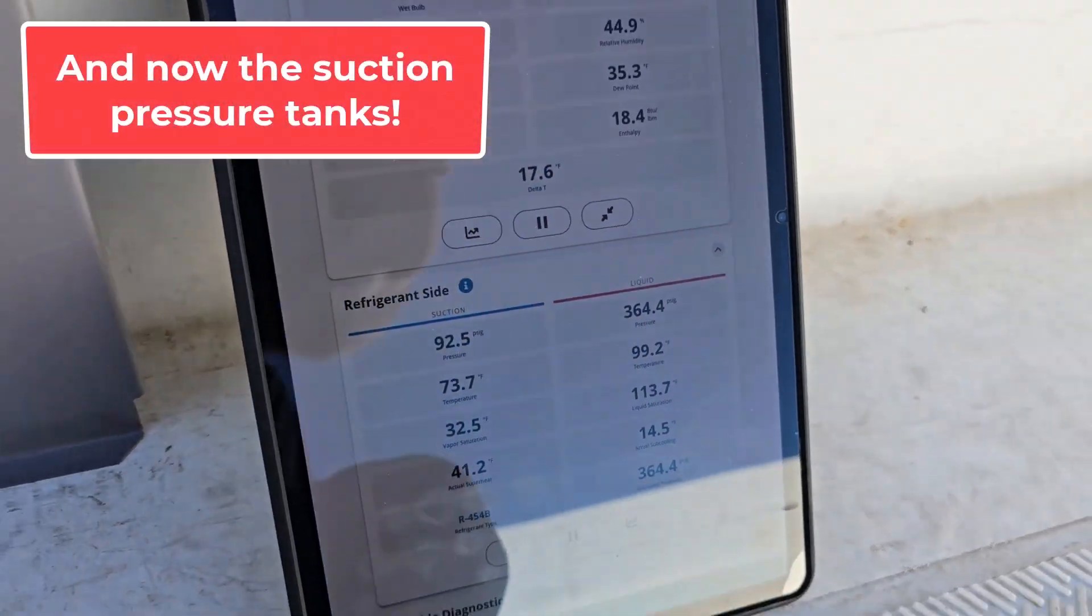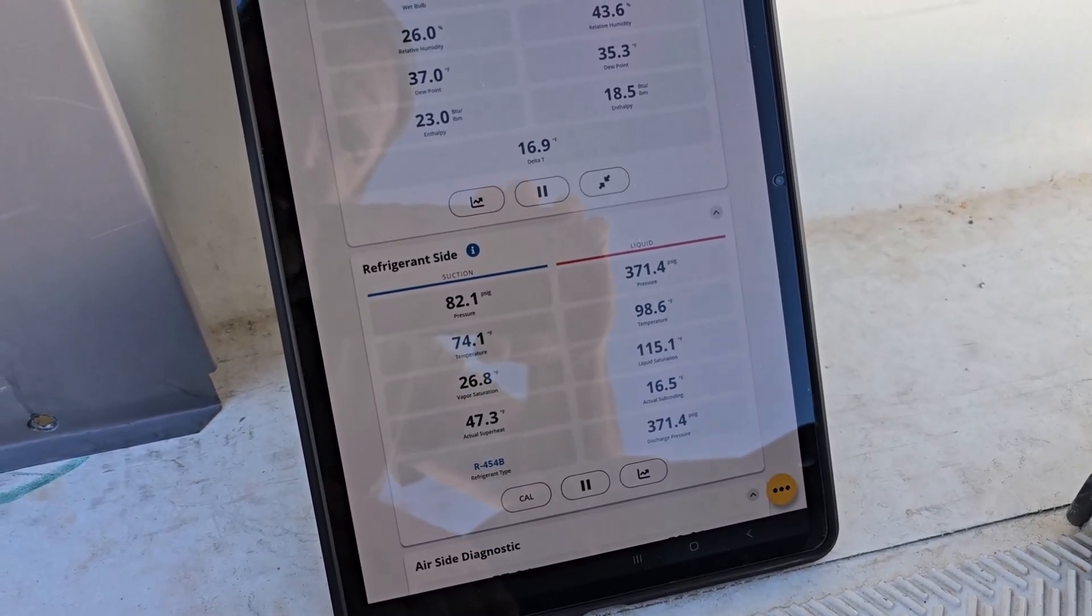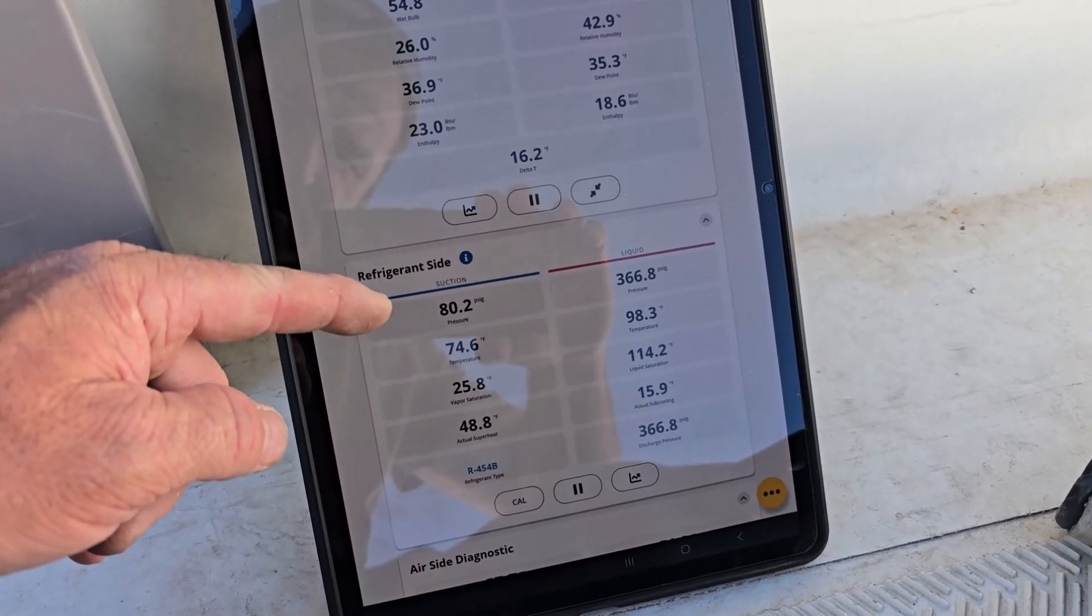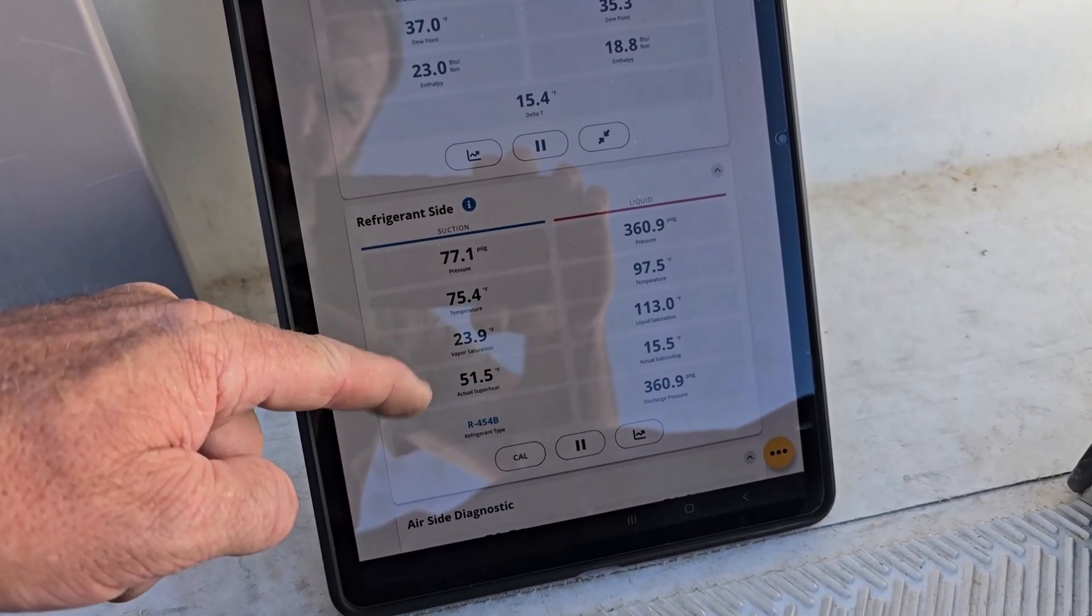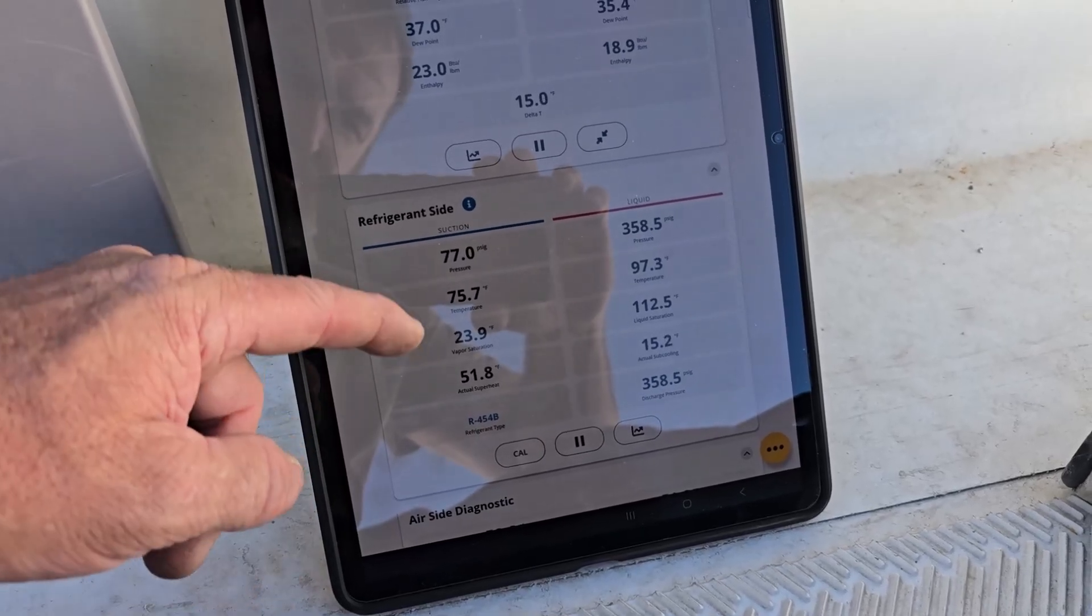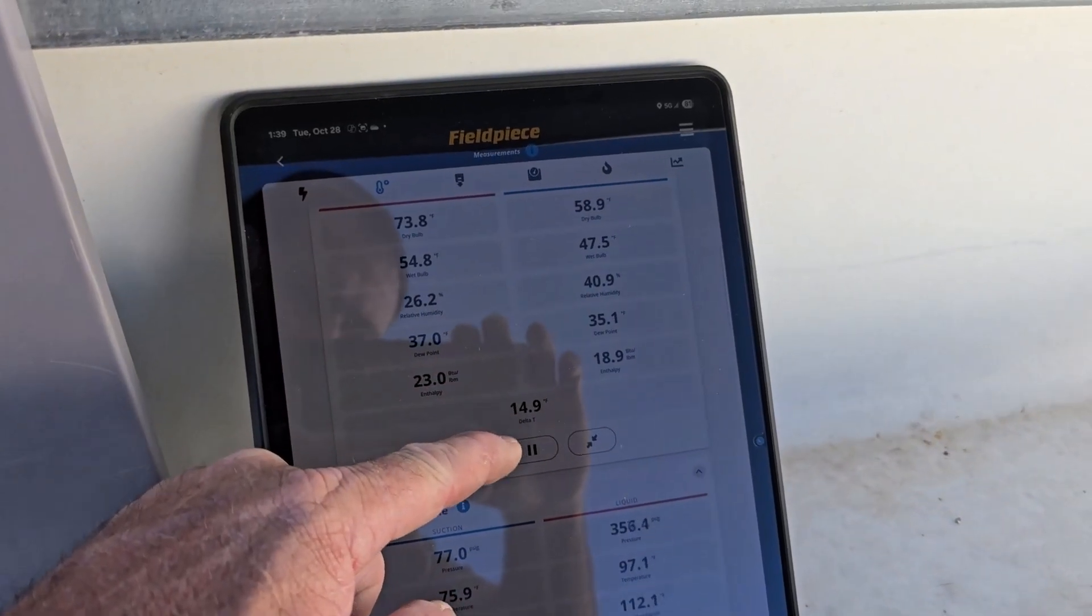You can see it's going to tank. That TXV might be pissed indeed. So far I haven't found any restrictions after any check valves. I do have to take one more temperature to confirm the last check valve, but we're looking at, this is tanking, this suction pressure is tanking. Vapor saturation is 24 degrees, so they will start frosting those feeders. Split temperature is 15 and dropping.